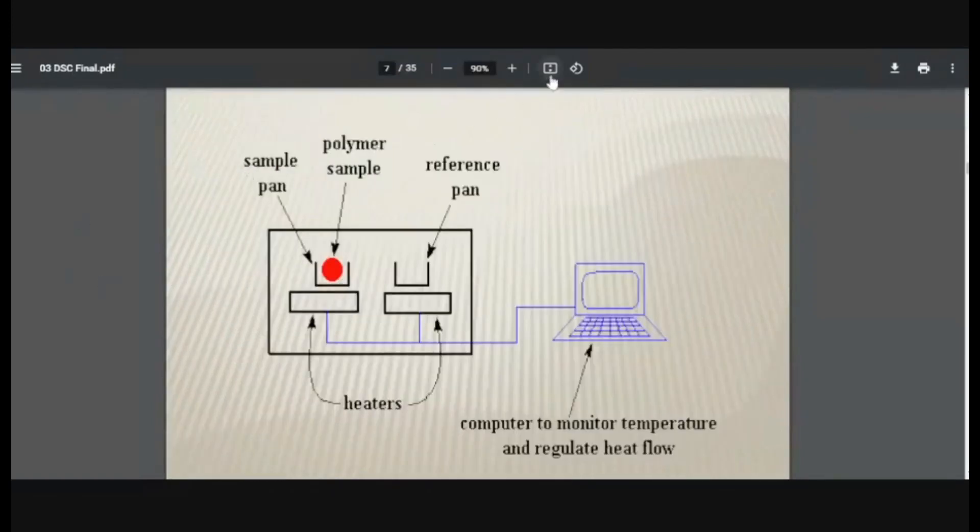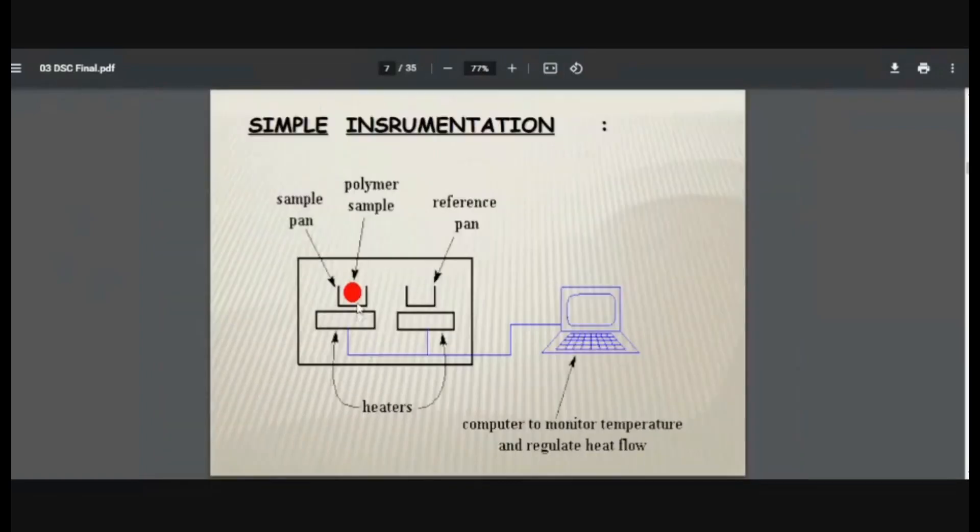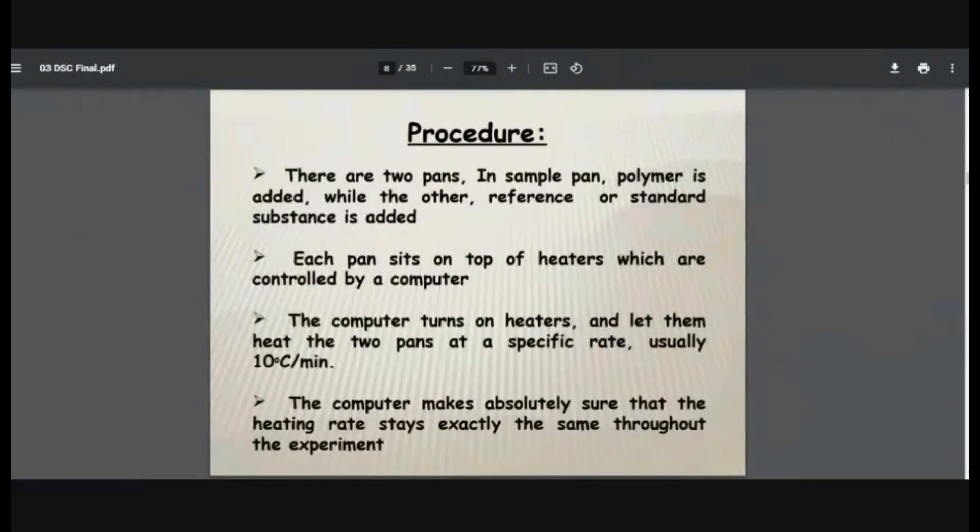Let us proceed then. This is how the instrument looks like. We have sample pan in which there is sample, say polymer is kept. There is reference pan. There may be some reference added, or it may be simply empty reference pan. Then there are two heaters provided. Both the heaters are attached to a monitoring system, differential scanning instrument. And so heat that is provided to both sample and reference pan is measured, and the difference is being calculated by the differential scanning calorimetry.